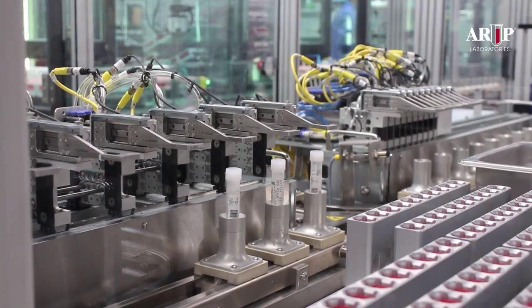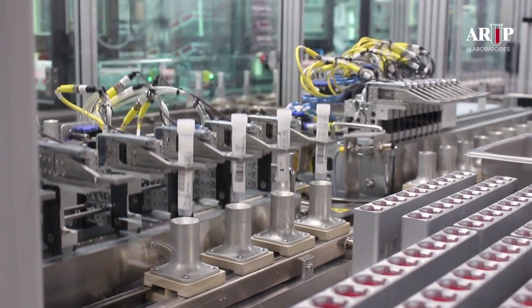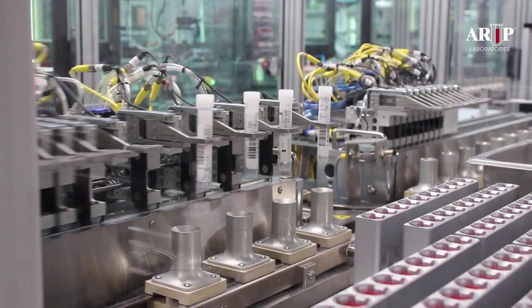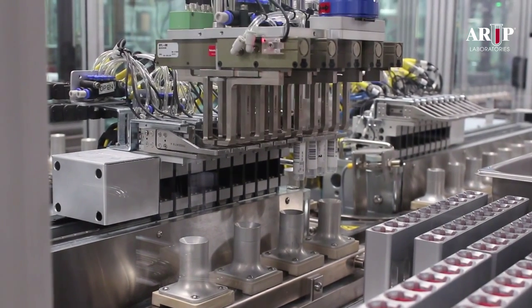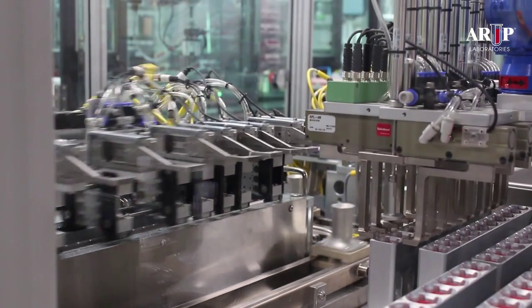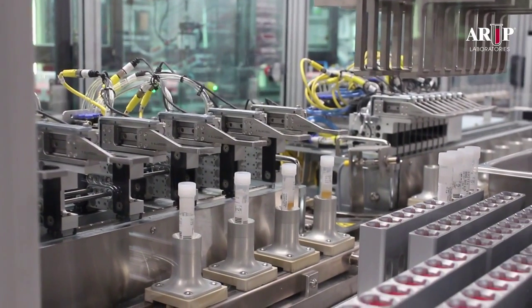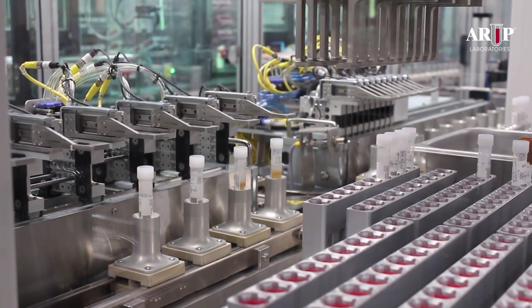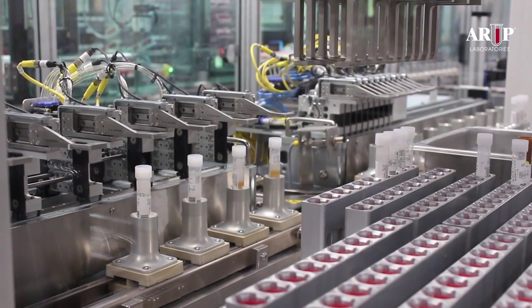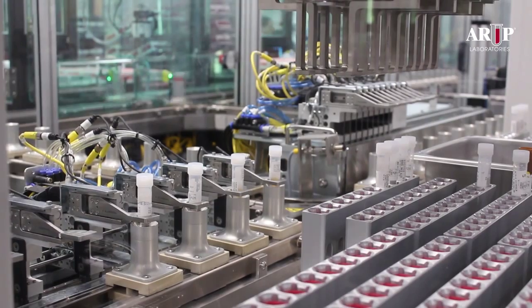From 1 to 10 tubes arrive in pucks on the automated track at a loading station next to the TMW. The tubes are spaced at intervals of about 3½ inches because of the repelling forces of the magnetic pucks. A robotic system lifts the tubes out of the pucks and moves them into intervals of only about 1 inch in order to be transferred to a 6-axis robot.